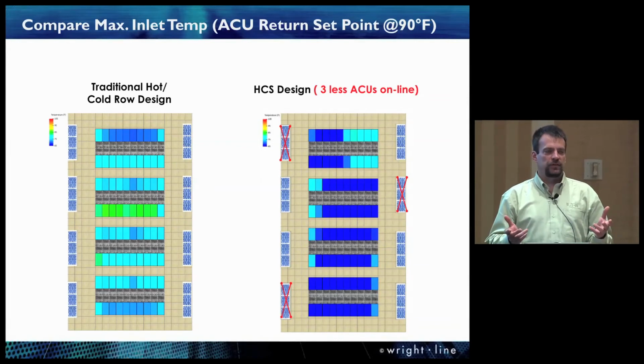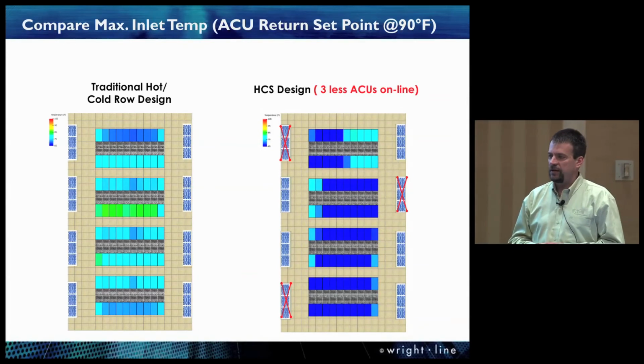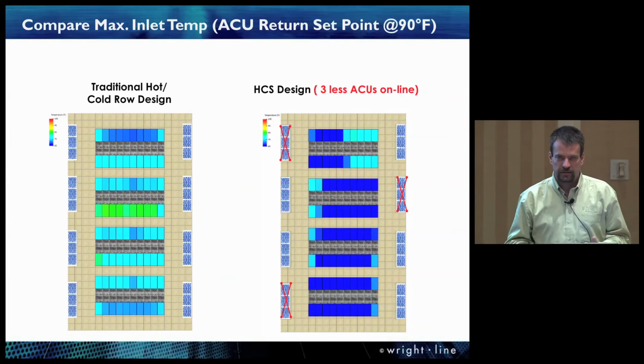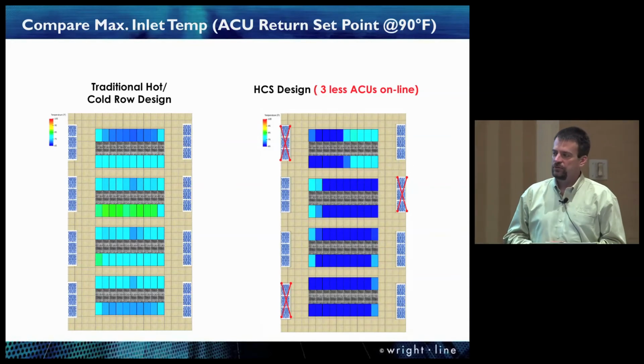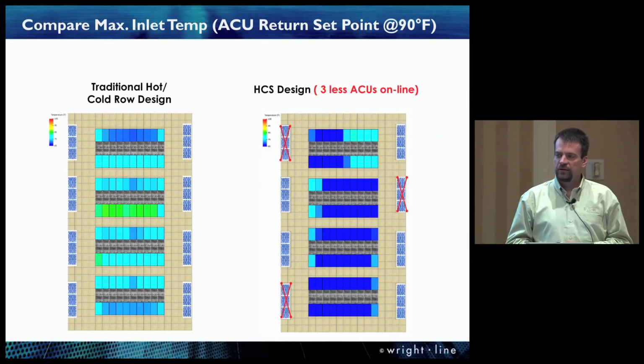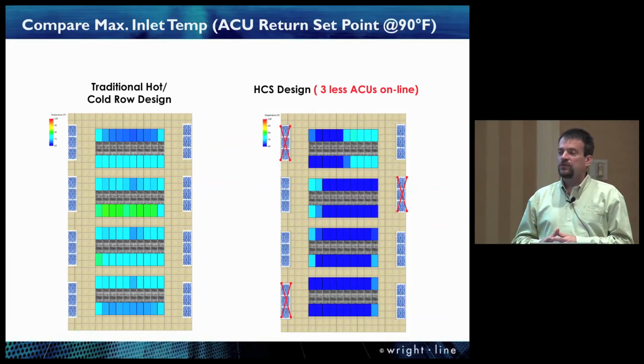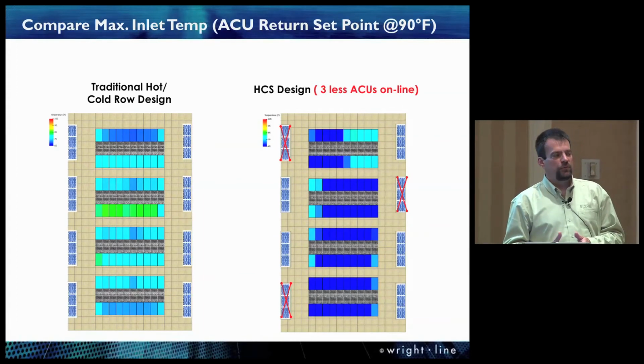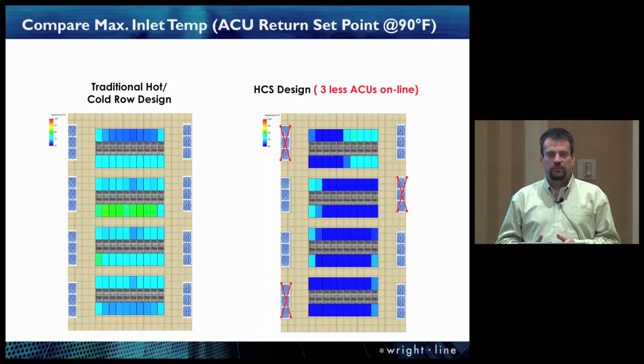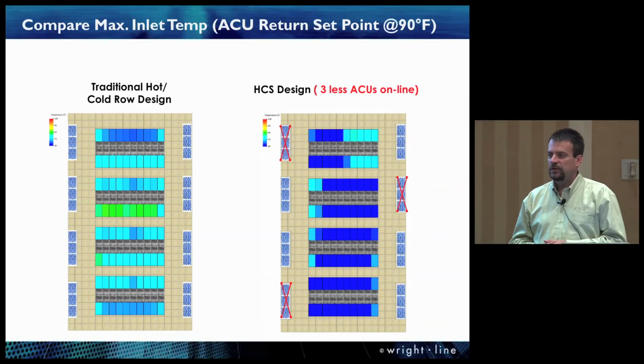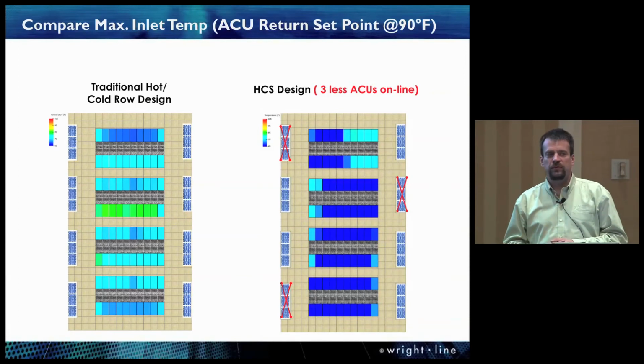Now you can look at this either way. You can be cycling CRACs that you already have, or you can not buy the 3 CRACs and save the operational cost as well as the purchasing cost of these CRACs. But as you look at the heat containment data center, you can see a lot more of the racks actually have a lower inlet temperature currently displayed through the CFD model.